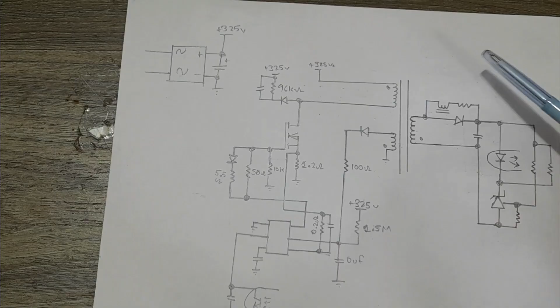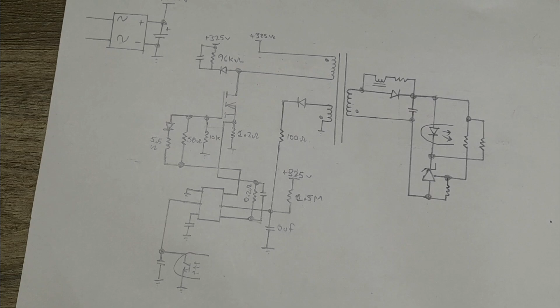So what happens is that the full current flows through the coil of the transformer, through the winding of the transformer, to the ground. This resistor will immediately blow up, the transformer will immediately blast or blow up, and in the process it will also damage the load, or it may not have enough time to damage the load, but a fuse may have been appreciated if it was there.